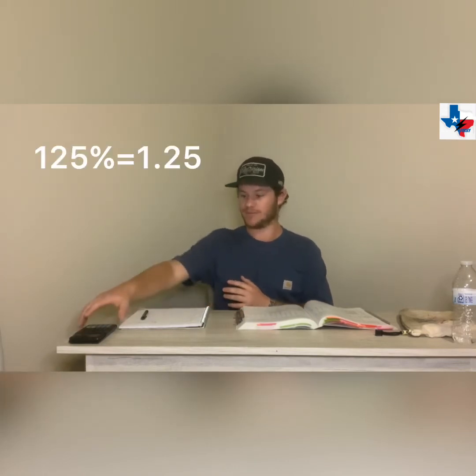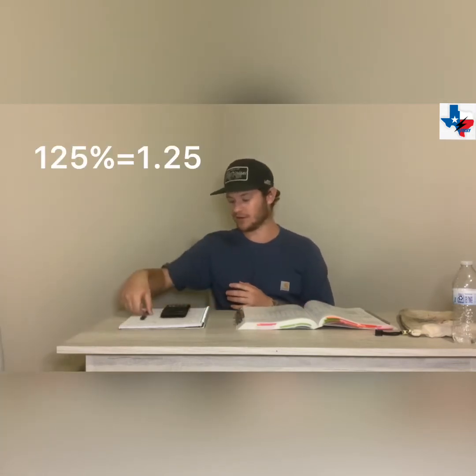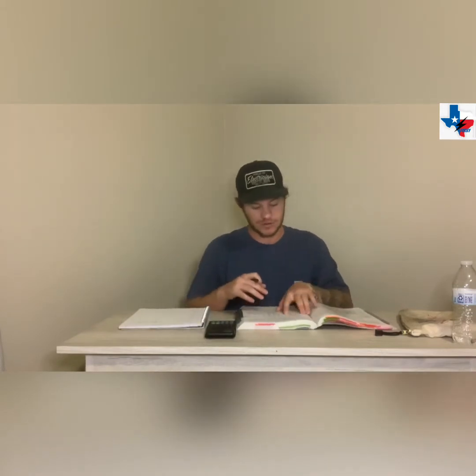So anyway, the first thing that we're going to do is we're going to size our wire. So like I said, these motors are continuous duty, 3 hours, 125%. So you're going to get your calculator and you're going to find what voltage and what horsepower. That's how you're going to cross-reference everything to find your full load current, full load amps, whatever you guys want to call it. So for a 50 horsepower 480 motor, it's 65 amps.